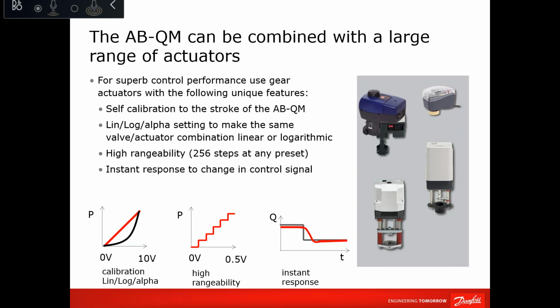And there will never be a gap between the spindle of the valve and the actuator operation, because otherwise there is a problem in controllability, and the lifespan of your actuator will also be compromised. Let's say the actuator is designed for 100,000 cycles. If you have a wasted range of 50%, half of the lifetime of the actuator is gone. So you need the actuator to only modulate the stroke of the valve. Clear?